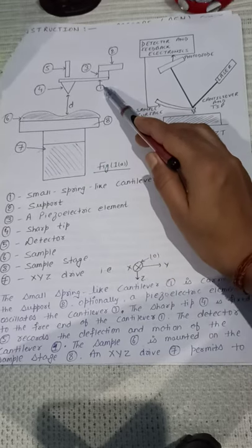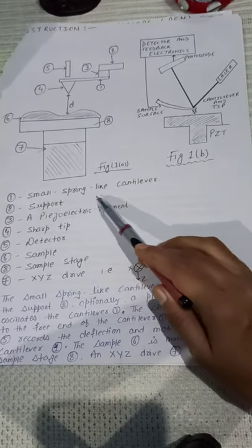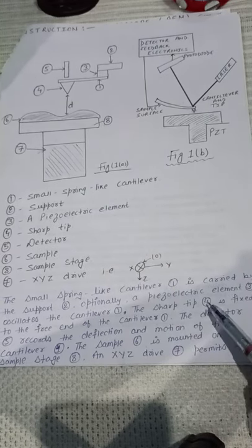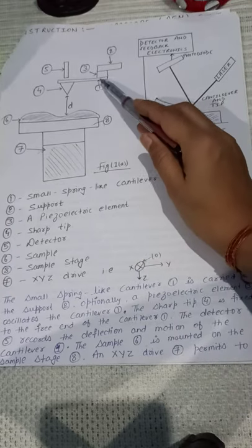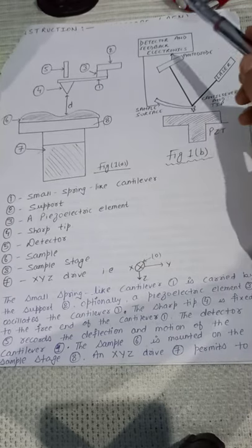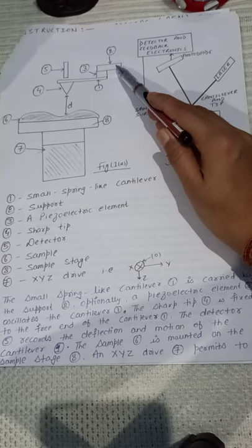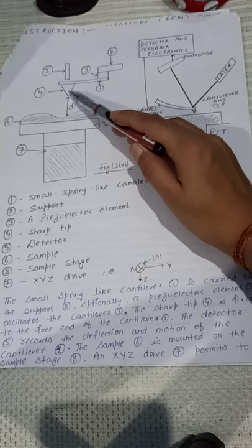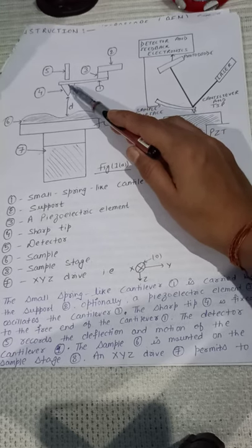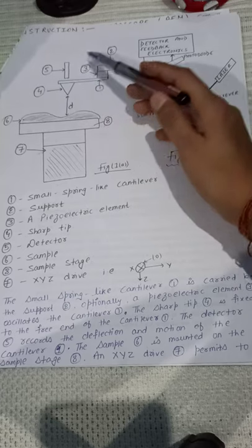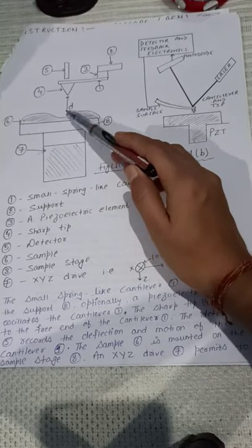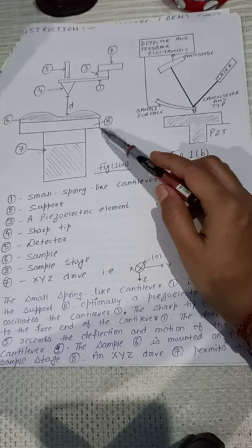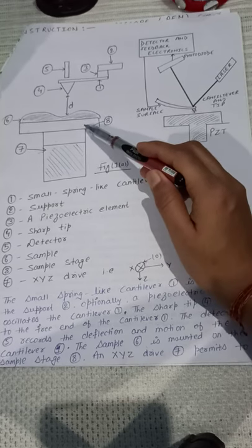Number 1 is a small spring-like cantilever, 2 is support, 3 is piezoelectric element, 4 is the sharp tip, 5 is detector, 6 is sample, 7 is XYZ drive, and 8 is sample stage.